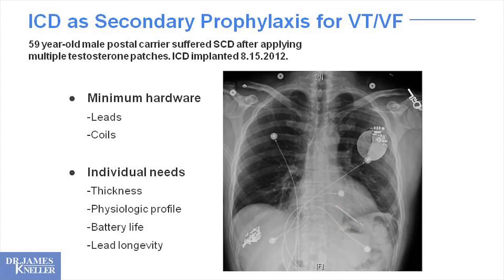the ICD coil. So should this device, battery and computer here, lead here, detect a dangerous rhythm, this device can try to forcefully pace the heart to stop that arrhythmia, and failing that, the capacitors charge up in the device and a shock is delivered between that coil and the can, as we say. So you have a huge jolt of electricity passing through all of that myocardium and resetting that rhythm to normal.